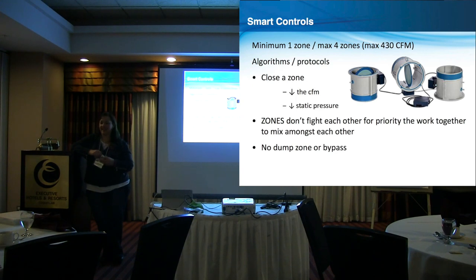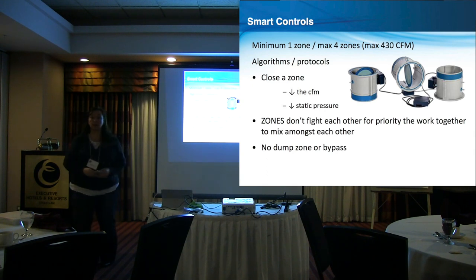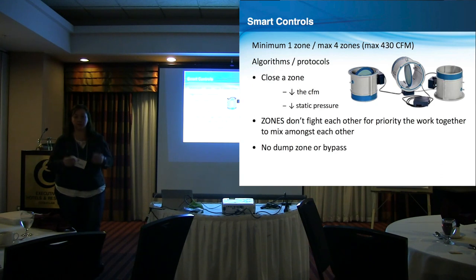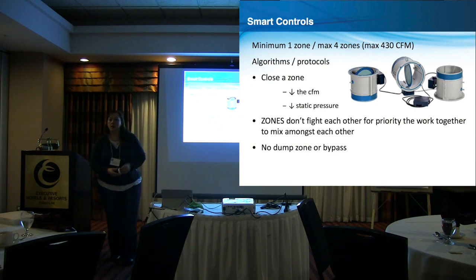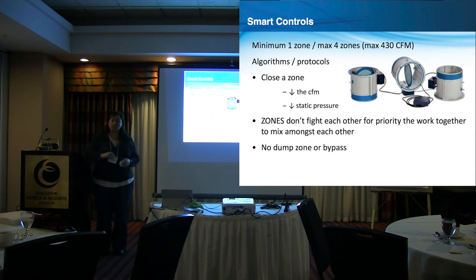So your total static is 0.6 to 0.8. Yeah, 0.68. And you're reserving some of that for return, so is your return still conventional low velocity? Contractors just size the returns conventionally. And then you've got your pressure drop, your coil, so on your supply deck you're probably around 0.4. Noel, do you know the answer to that? I looked it up on my calculator and put 430 on the 8-inch pipeline. I guess around 0.4. I think the question, Michelle, is whether 0.68 is total external, or do you have to, as Paul suggests, subtract your air conditioning coil from that external allowance?